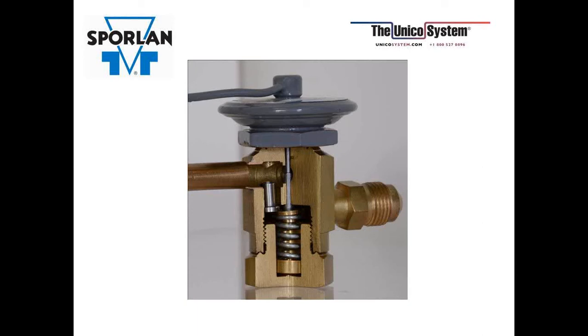And then you have the drill hole for a port. Then you have your push rod and pin combination. You have your superheat spring, the spring guide, and over here is the little poppet for the check valve. So in the normal direction of flow, the refrigerant will come from left to right.